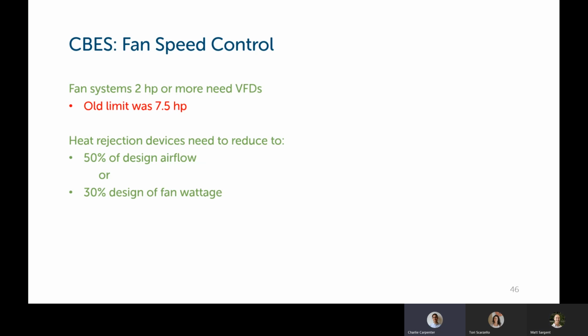For fan speed control, any fan system 2 horsepower or more needs to have a VFD on it. The requirement in the current code was 7.5 horsepower. So again, that horsepower rating's been reduced. So VFDs will be required on many more fan systems. Heat rejection devices need to reduce their fan speed to at least 50% design airflow or 30% fan design wattage. I believe that is the same requirement as the previous code, but I'm just noting that again.